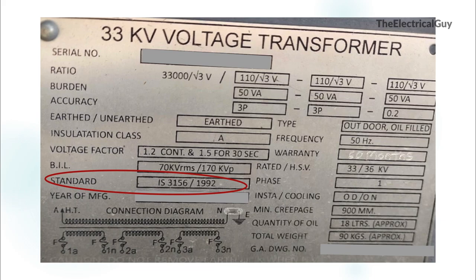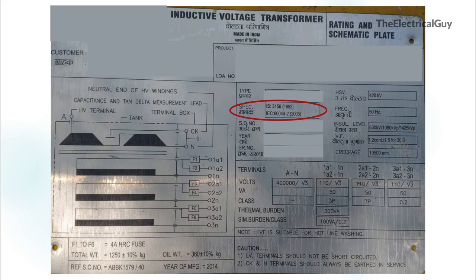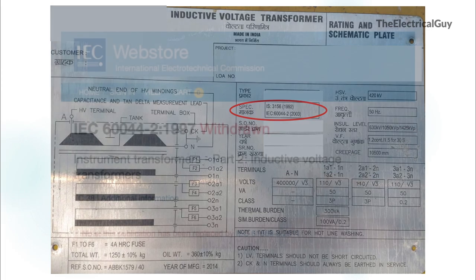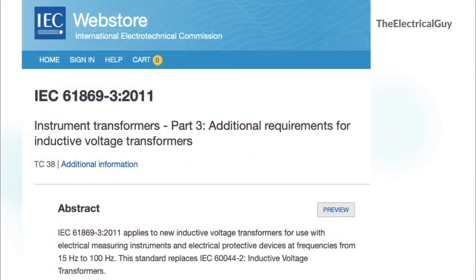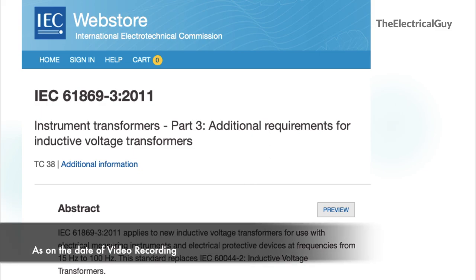IS stands for Indian Standard, and this standard specifies the general requirements applicable for voltage transformers. On the nameplate of the 420kV IVT, the reference standard is mentioned as IEC 60044-2. IEC stands for International Electrotechnical Commission. If you search this IEC on the official website, you will find that it has been withdrawn and is now replaced by IEC 61869-3, which covers additional requirements for inductive voltage transformers. So the latest IEC standard for IVTs is IEC 61869-3.